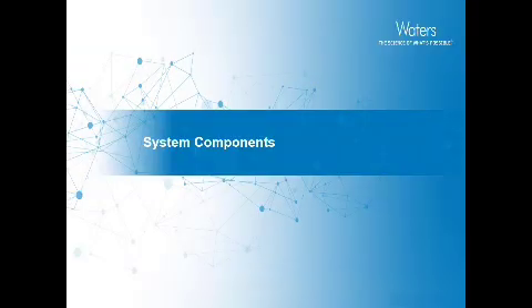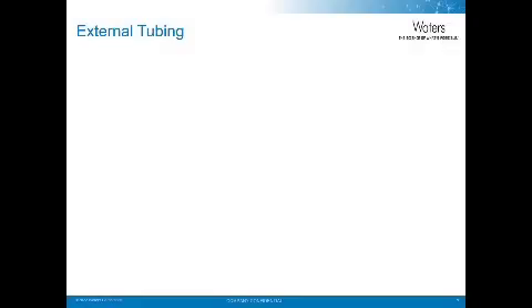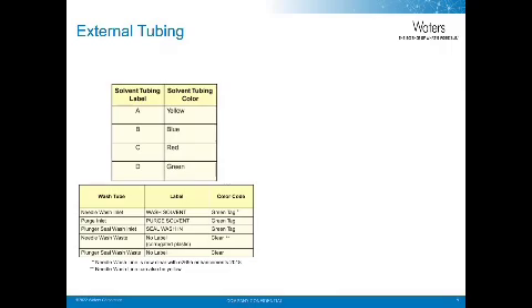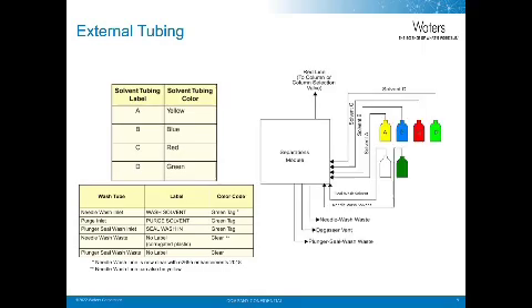Now let's take a look more closely at all of the components of the system. Once again, we will explore each component in the order the mobile phases travel through the system. So first, we'll take a look at the external tubing. The solvent tubing is usually colored depending on which line it is, but even if it's not colored at the customer sites, the lines should be labeled. The picture to the right shows all the lines, including the red line going to the column or column selection valve, depending on the configuration.